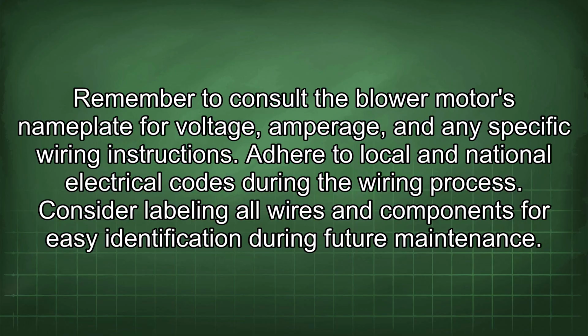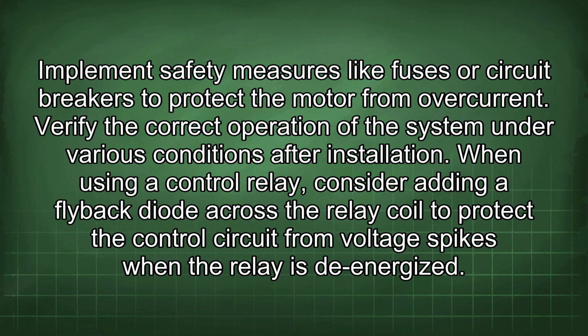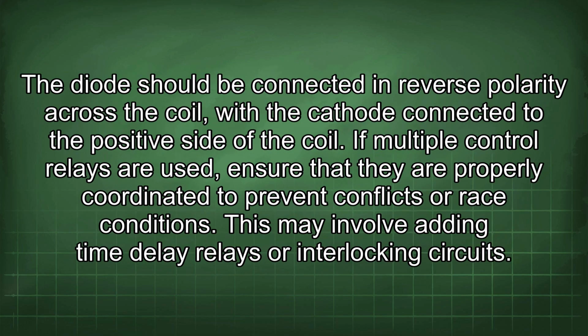Consider labeling all wires and components for easy identification during future maintenance. Implement safety measures like fuses or circuit breakers to protect the motor from overcurrent. Verify the correct operation of the system under various conditions after installation. When using a control relay, consider adding a flyback diode across the relay coil to protect the control circuit from voltage spikes when the relay is de-energized. The diode should be connected in reverse polarity across the coil, with the cathode connected to the positive side of the coil.